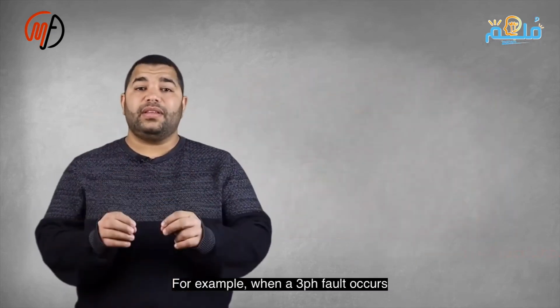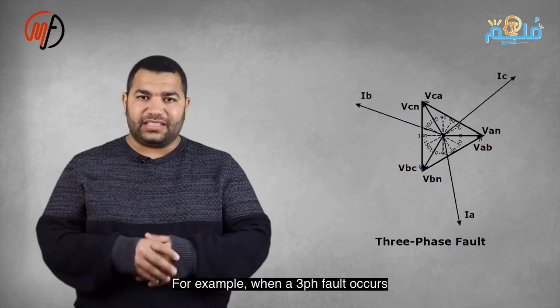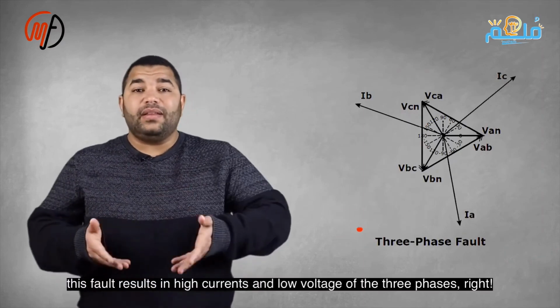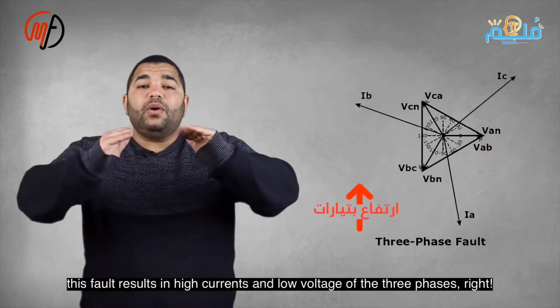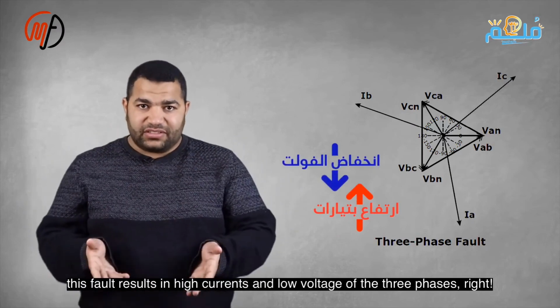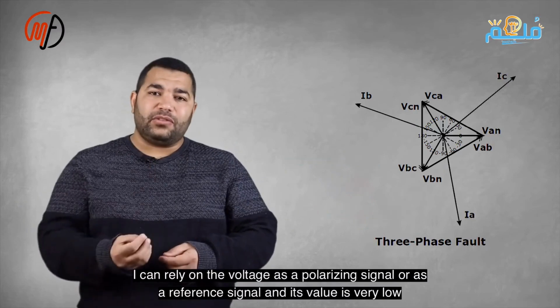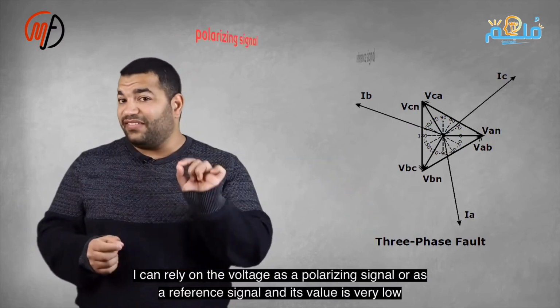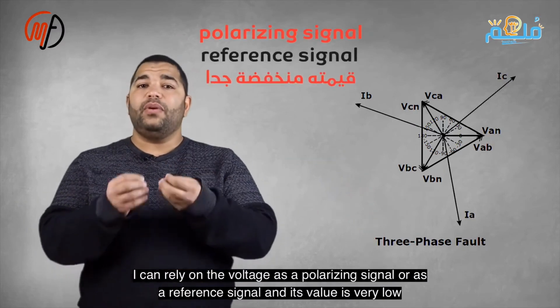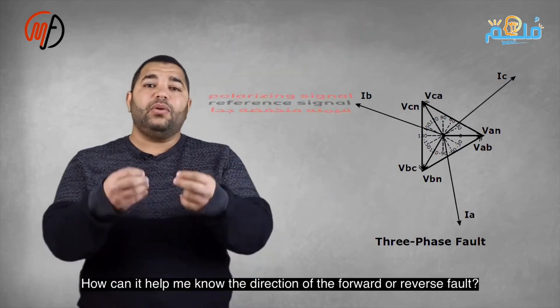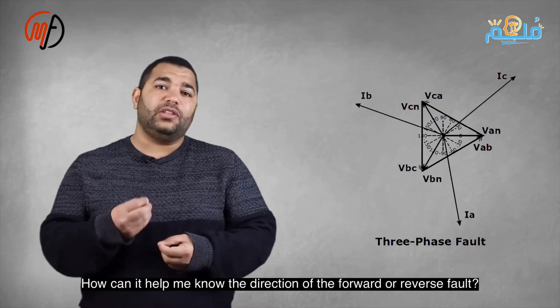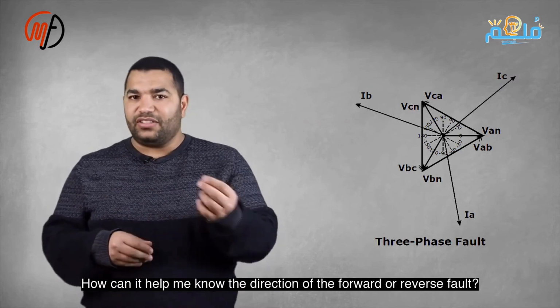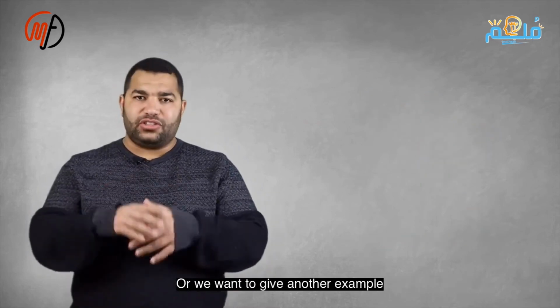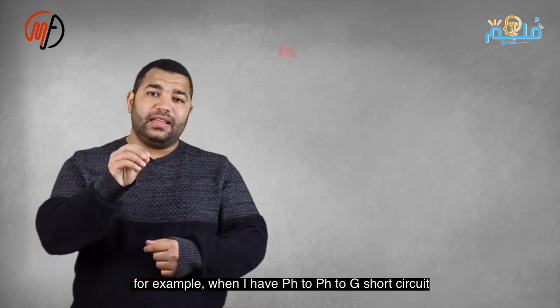The directional protection needs 3 conditions to be met as an AND gate. A 3-phase fault causes a rise in current and a drop in voltage. How can I rely on low voltage to determine fault current direction? Is it forward or reverse? A phase-to-phase fault changes some voltage angles, affecting zones, leading the relay to misinterpret fault direction. A high impedance fault generates low current below the directional protection setting. Directional protection needs current, voltage, and angle conditions met. If fault current is below the setting, it won't operate.